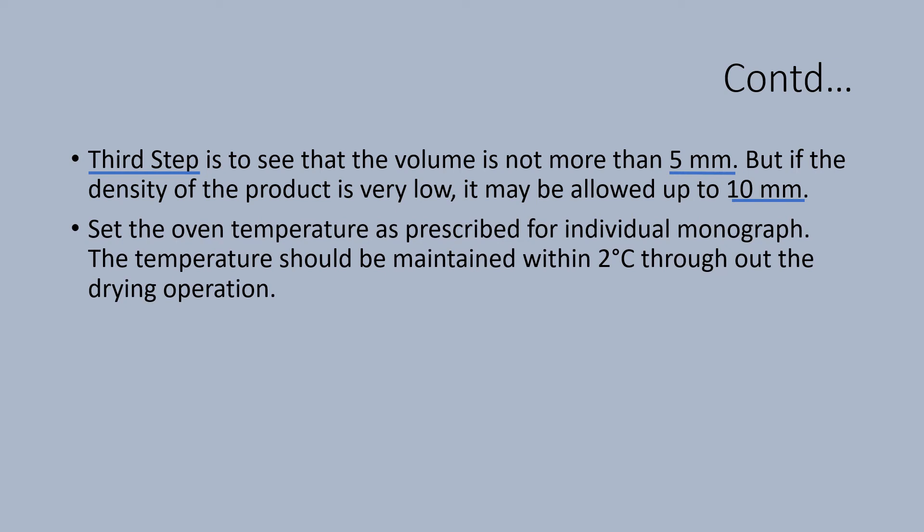Set the oven temperature as prescribed in the individual monograph. The temperature should be maintained within 2 degrees centigrade throughout the drying operation. This must be done much before the start of the test. By the time you start the test, the oven should be ready with the required temperature. It is also important to see that the temperature is maintained within 2 degrees centigrade throughout the analysis. Data loggers with a provision to record the temperature at a specified interval, say every half an hour, is recommended as an objective evidence that the temperature is maintained throughout the test.